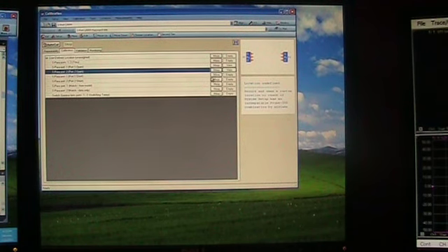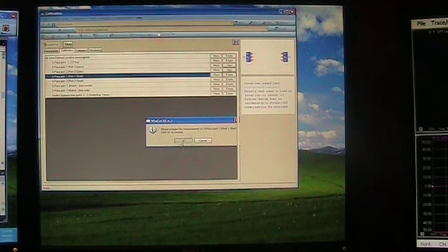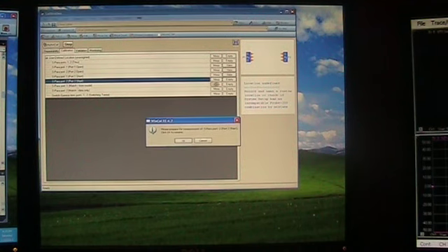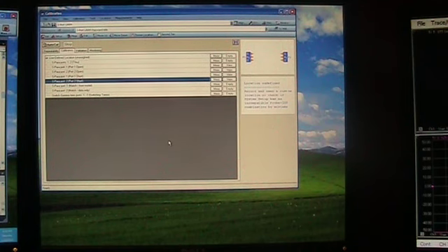Okay, I've moved over to the shorts. So we're going to go ahead and measure port 1 short, port 2 short here in a moment. If you're not familiar with WinCal, this is Cascade Microtech WinCal XE. And more information can be found at cmicro.com. And it's a pretty fantastic product.